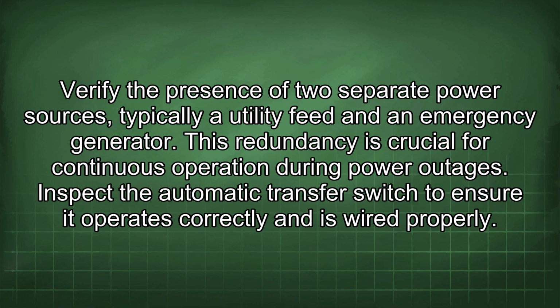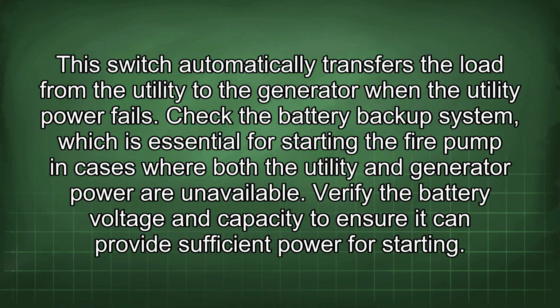Inspect the automatic transfer switch to ensure it operates correctly and is wired properly. This switch automatically transfers the load from the utility to the generator when the utility power fails. Check the battery backup system, which is essential for starting the fire pump in cases where both the utility and generator power are unavailable. Verify the battery voltage and capacity to ensure it can provide sufficient power for starting.